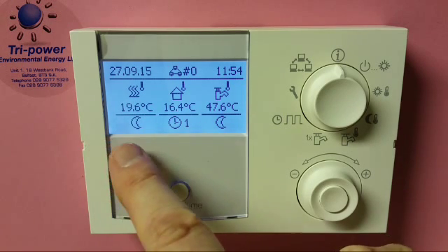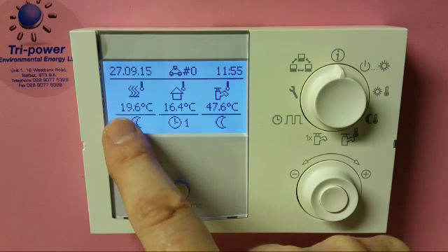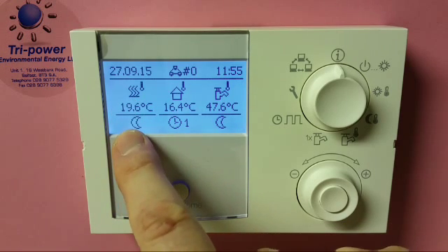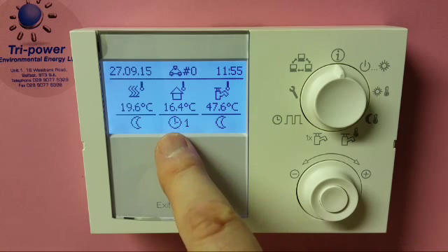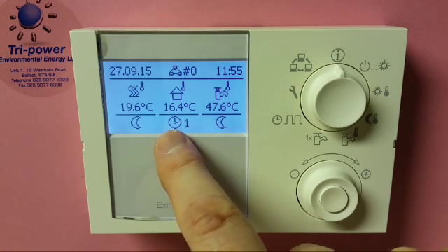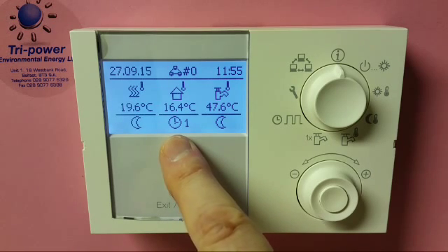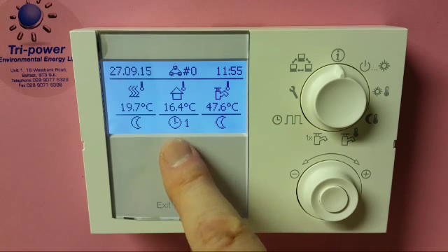On this display, on the left hand side, you have 19.6, which is your heating temperature. This is the air temperature, not the water temperature. It says here this moon means that it's on setback. The clock says 1, which means you're on time program 1. You have 2 time programs with this boiler. It means that you can set these and switch between them, so that you don't have to reprogram everything all of the time. For instance, when you're working or when you're on holiday, you can switch between these functions.